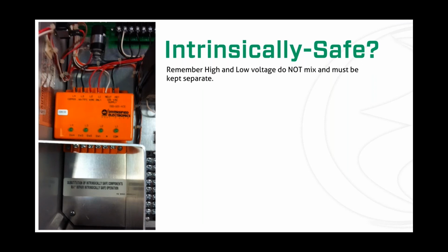But again, what this guy does is it is going to step voltage down so low, and this is going to be going to your float switches, the wiring to your float switches. It's going to step the voltage down so low that even if you had an environment down in your pit that was full of explosive gases of some sort, even if, say, one of these float wires got cut or nicked or even shorted out down there, they could not produce a spark hot enough to ignite the gases. So obviously this is a very important thing.